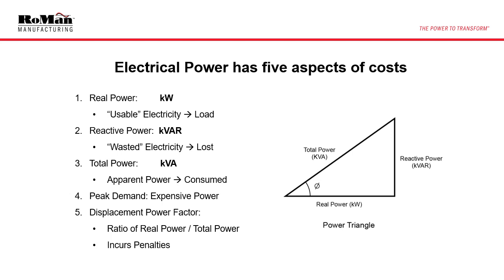The power triangle here shows reactive power and real power 90 degrees out of phase. They are summed up vectorially to give us total kVA. The angle this triangle forms, or theta, is our displacement power factor. Peak demand is the highest usage charge. This is the ability to use more power than is normal in an operation.